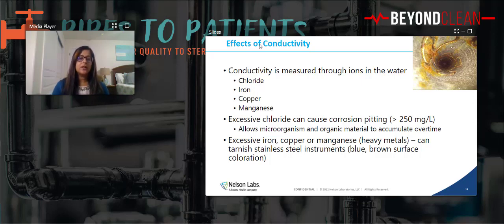Effects of conductivity: conductivity is a measurement of ions in the water, things like chlorides, iron, copper, manganese, the heavy metals going into the water. These ions are very harsh on the metals and materials used to make reusable devices. Although they use medical grade stainless steel, medical grade silicone, medical grade polypropylene, PEEK, all of these materials still get affected by ions and you will see stress cracking. So even if it's medical grade, it really doesn't matter.